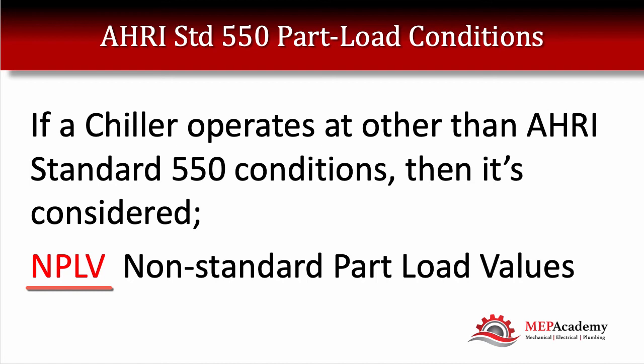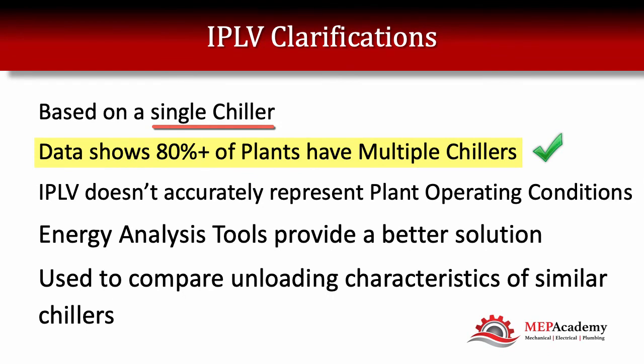NPLV applies when operating conditions don't fit within the AHRI Standard 550 parameters, which most real-world installations won't. This video covers the IPLV calculation. It's based on a single chiller, yet most data shows 80% or more of plants have multiple chillers. So IPLV doesn't accurately represent plant operating conditions — energy analysis tools provide a better solution.